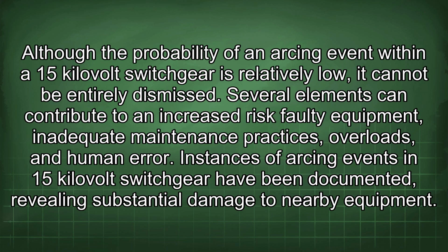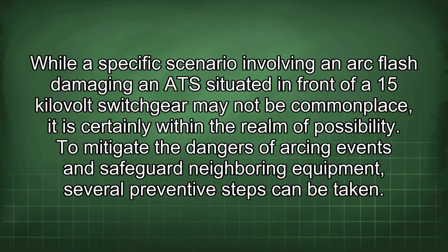Although the probability of an arcing event within a 15 kilovolt switchgear is relatively low, it cannot be entirely dismissed. Several elements can contribute to an increased risk: faulty equipment, inadequate maintenance practices, overloads, and human error. Instances of arcing events in 15 kilovolt switchgear have been documented, revealing substantial damage to nearby equipment. While a specific scenario involving an arc flash damaging an ATS situated in front of a 15 kilovolt switchgear may not be commonplace, it is certainly within the realm of possibility.